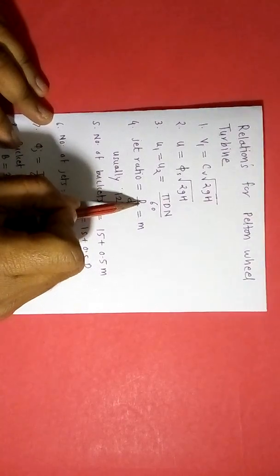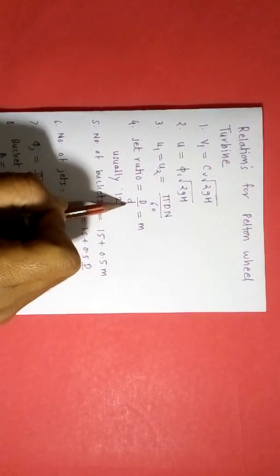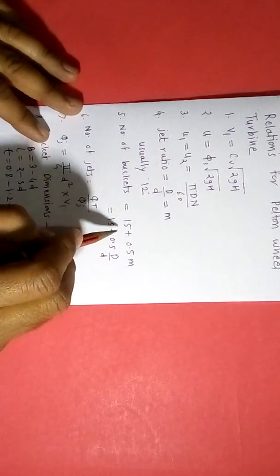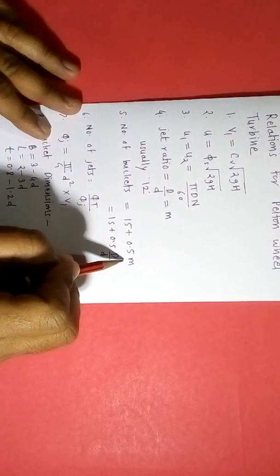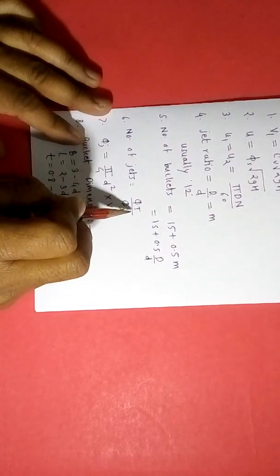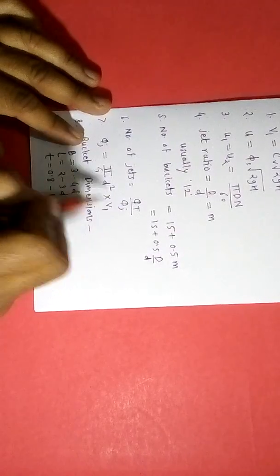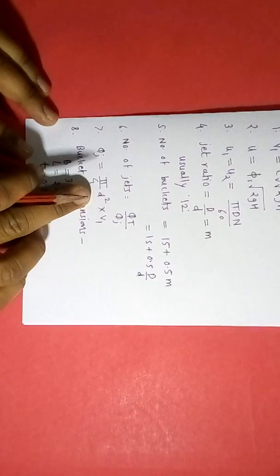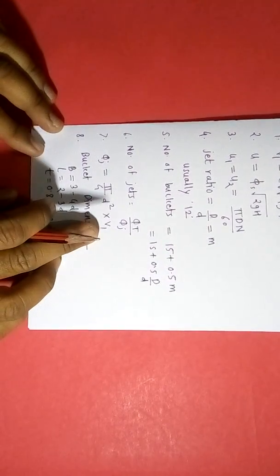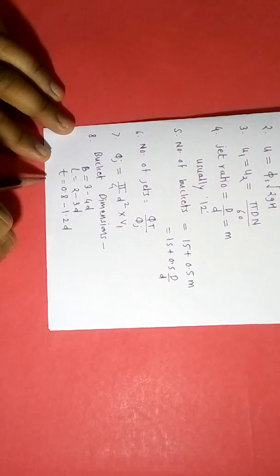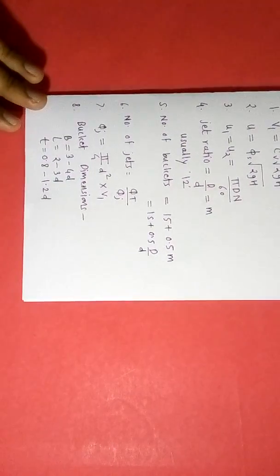There is a term called jet ratio, which is the ratio of rotor diameter to jet diameter, and it is usually 12. The number of buckets equals 15 plus 0.5m, where m is the jet ratio. The number of jets is given by total discharge divided by discharge through a single jet, and discharge through a single jet is pi/4 times D-squared times jet velocity. Bucket dimensions include relationships for width, length, and thickness.